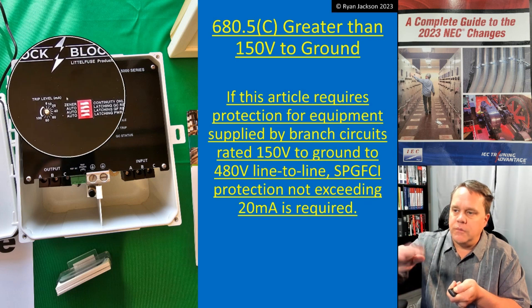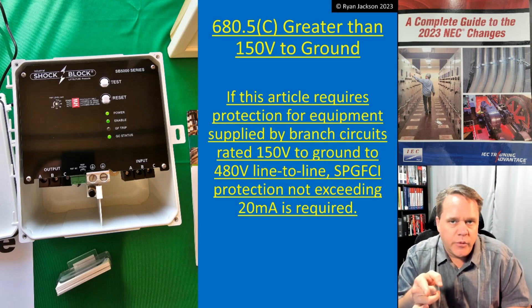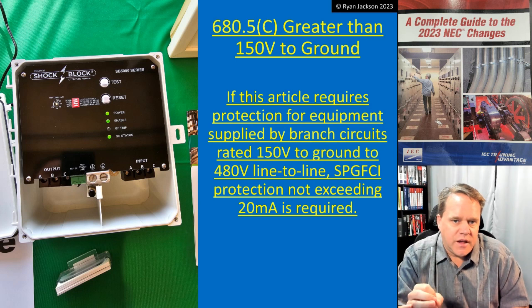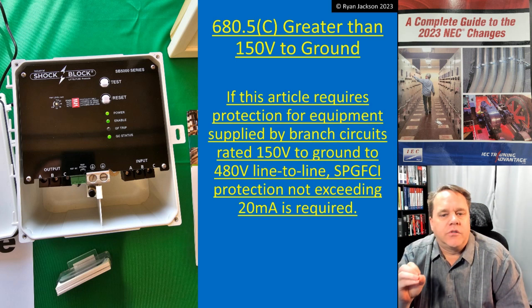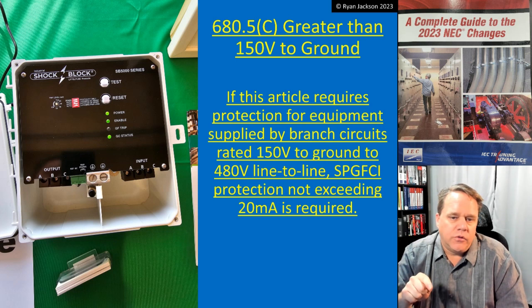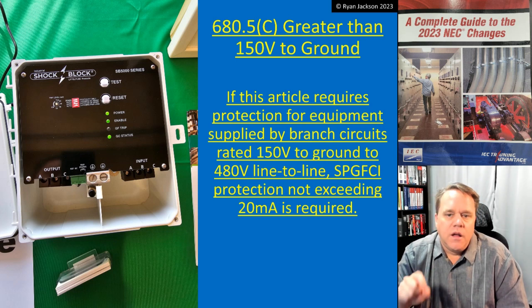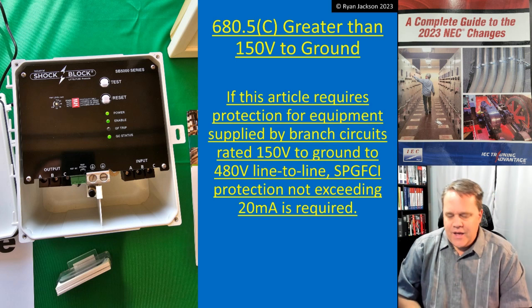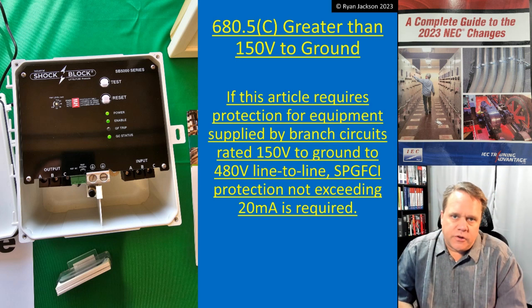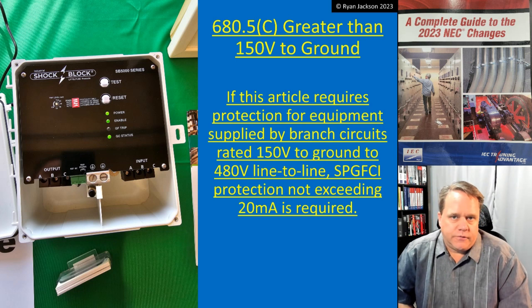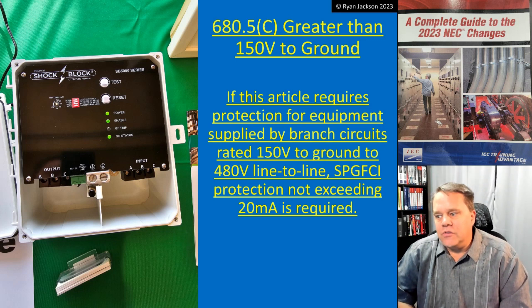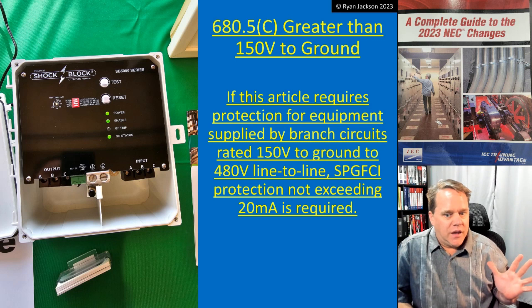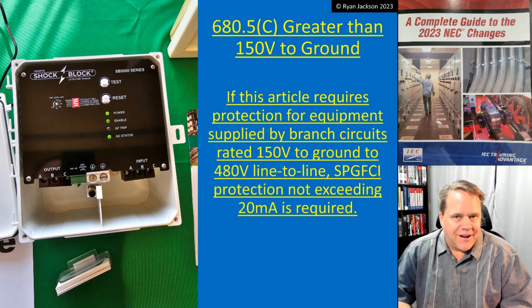If we read what the code says: if Article 680 requires protection for equipment supplied by branch circuits rated 150 volts to ground and 480 volts line to line, then SP GFCI protection not exceeding 20 milliamps is required. So if we're in a swimming pool, most of us would agree we want GFCI protection for the motor. I'm really not interested in swimming in a pool without GFCI protection — a 120-volt swimming pool motor without GFCI is spooky enough; a 480-volt three-phase motor is even more concerning.